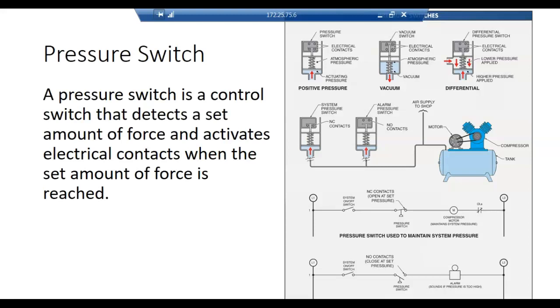Pressure. We have pressure sensors on both lines, and we have different methods we can use. Anybody that has a compressor at their house can relate to these. We're about to hear one in a minute. There's a pressure sensor on this compressor, and when it gets up to a certain pressure, it'll cut it off. Then when it gets down to a certain pressure, it'll turn back on. So it's got an upper and lower limit also.